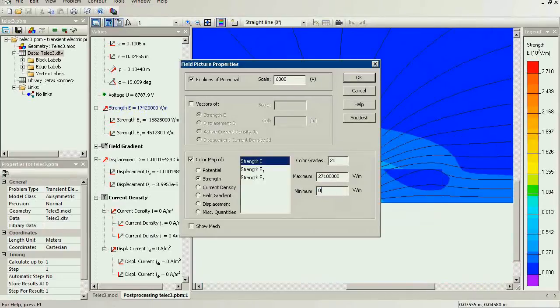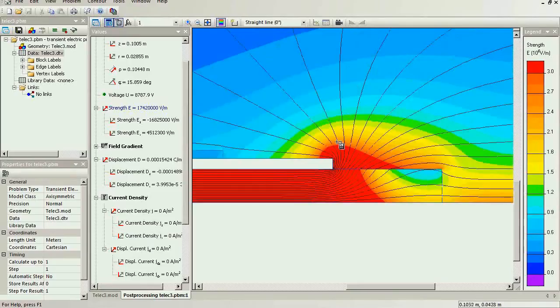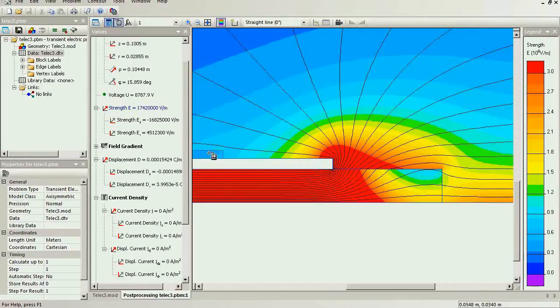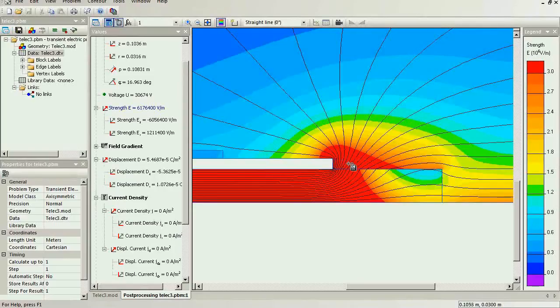To show you better, I will adjust the field picture and adjust the scale. This is the breakdown voltage of the air. Here is the conductor, conductor surface, insulation, shielding and the cover. And in the place where the shielding is terminated, the electric field stress is very high.